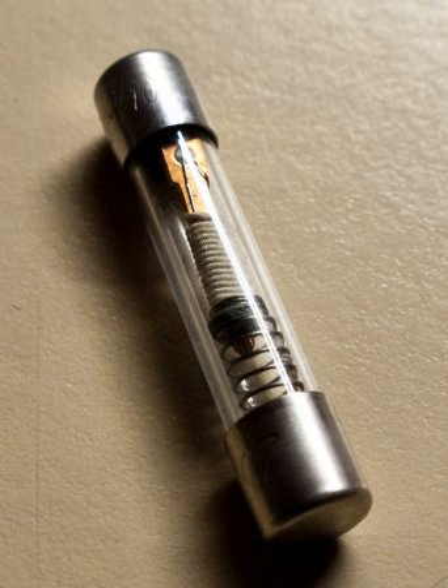The fuse elements may be shaped to increase heating effect. In large fuses, current may be divided between multiple strips of metal. A dual-element fuse may contain a metal strip that melts instantly on a short circuit, and also contain a low-melting solder joint that responds to long-term overload of low values compared to a short circuit. Fuse elements may be supported by steel or nichrome wires, so that no strain is placed on the element, but a spring may be included to increase the speed of parting of the element fragments. The fuse element may be surrounded by air, or by materials intended to speed the quenching of the arc. Silica sand or non-conducting liquids may be used.